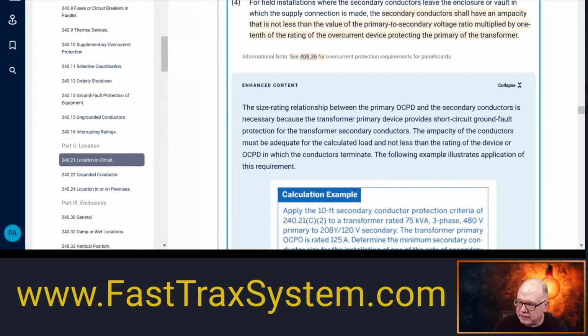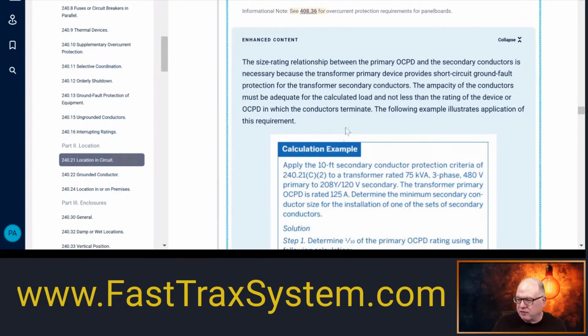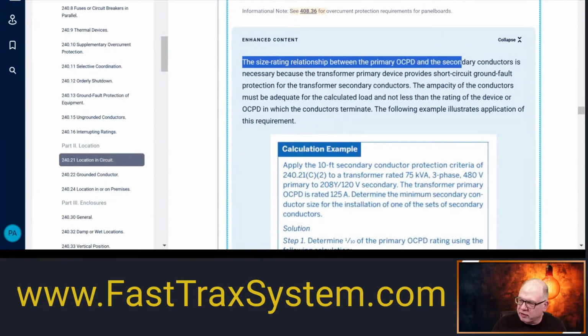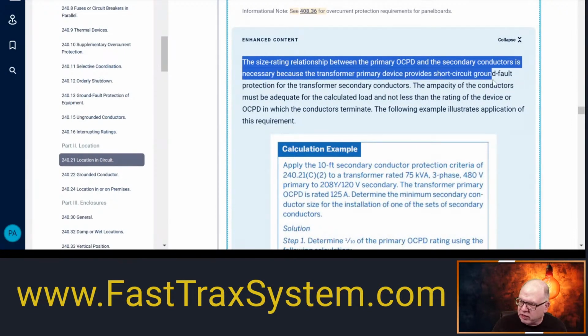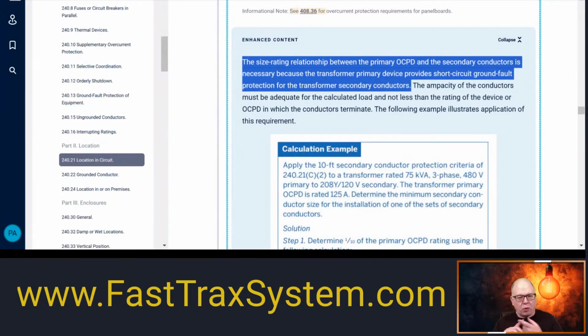So anyway, we want to look at this and see what the example is. So the size rated relationship between the primary overcurrent and the secondary conductors is necessary because the transformer's primary device provides short circuit ground fault protection to the transformer's secondary conductors. It is also important to understand that when we have that item number 4, we're making sure that at least the conductors are going to be a certain size. They probably are going to be larger, but they're at least a certain size in order to make sure that they're also adequately protected as well.